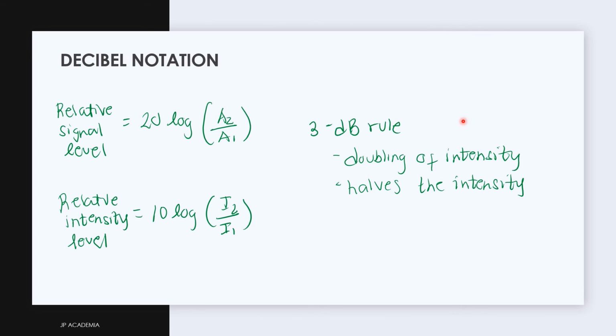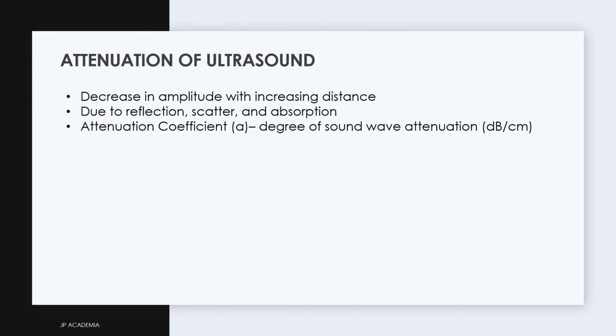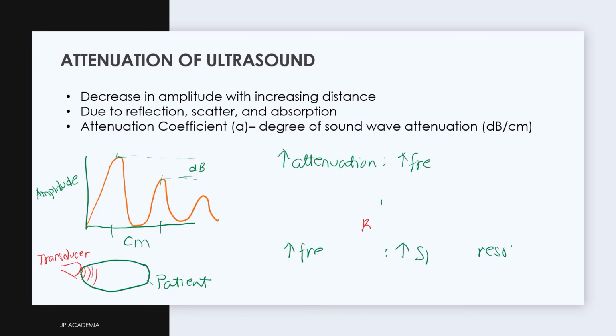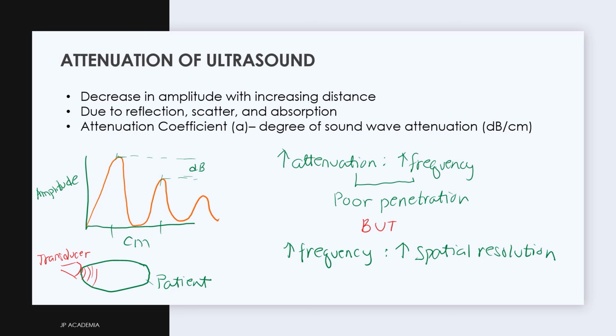One thing to note here at the right is the decibel notation in the 3 decibel rule. A 3 decibel increase multiplies the intensity by 2. If there is a decrease by 3 decibels in intensity, the intensity value will be divided by 2. And this is useful in adjusting the amplification or gain of the instrument. Sound waves get attenuated as they traverse the medium, and this is generally described as a decrease in amplitude as a function of distance. Some sources of attenuation include reflection, scattering, and absorption that produces heat.